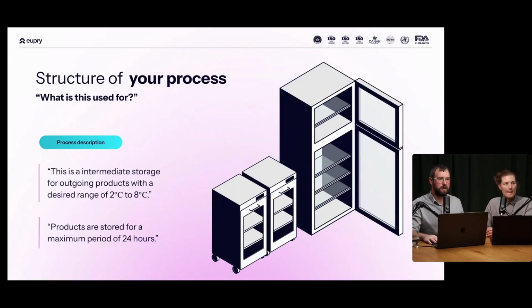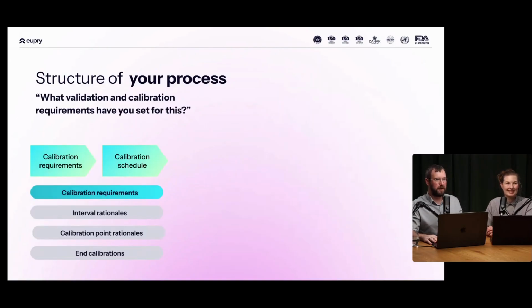So moving on - what validation and calibration requirements have you set for this fridge or whatever it might be? Calibration requirements actually feed into validation as well, because if you do a mapping, you would usually do it with calibrated sensors. You need to understand, especially for mappings, whether you want the end calibration as discussed before. The calibration requirements for continuous or continual monitoring in your equipment or facility would again have to be set based on your process.